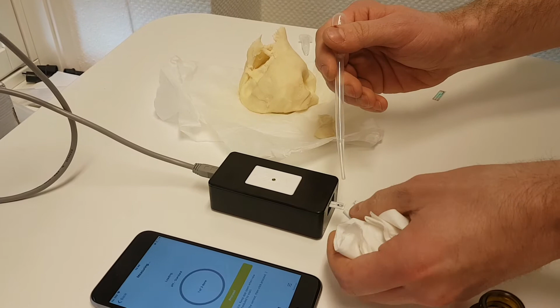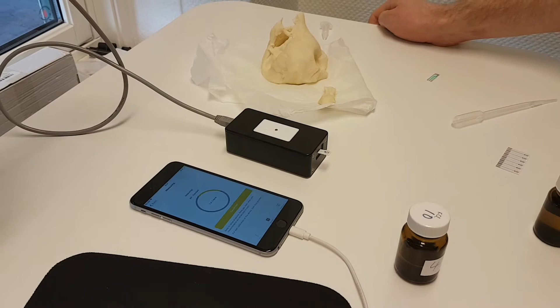So if you are very particular about the calibration, you can do this 3 times, and that should effectively flush away all of the old solution. Alright, so now we've introduced our pH 4 calibration solution, and we're going to hit proceed. And what this is going to do is generate an in situ calibration. So this works best if the medium that you're going to measure for your unknown sample is more or less similar to the ones in the calibration solution. If you don't have that, you will still get a correct result, but it's not going to be as accurate.